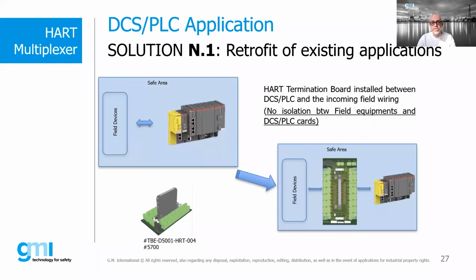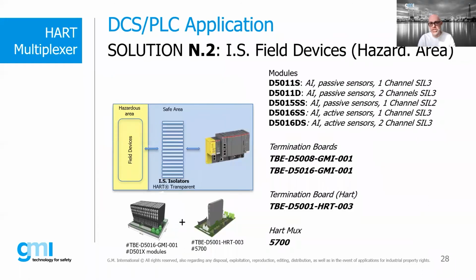The second solution foresees the integration of the GMI HART system into applications where intrinsic safety is involved. In this case, the HART MUX, through a special termination board, model TBE D5001 HRT003, equipped with a special connector, connects to the system termination board where the intrinsically safe barriers are housed for the management of sensors positioned in the hazardous area. In addition, connection of the HART system is allowed to 8 or 16 position termination boards for managing up to 32 channels for termination boards.